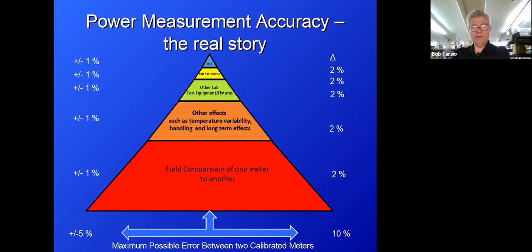I said, well, what's between the two meters? Well, there's a switchless combiner, and there's some transmission line, and it's warm in spots. I said, well, there's where your power's going. In other words, there are other effects. So the difference was, I calculated it for him. He gave me the power readings for the 2 meters, and it was about 5% delta between the two.